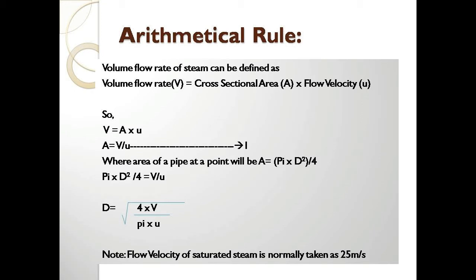Substituting the area expression into the equation gives: πD²/4 = V/U. Rearranging, D equals the square root of (4V divided by πU). Note that the flow velocity of saturated steam is normally taken as 25 meters per second.